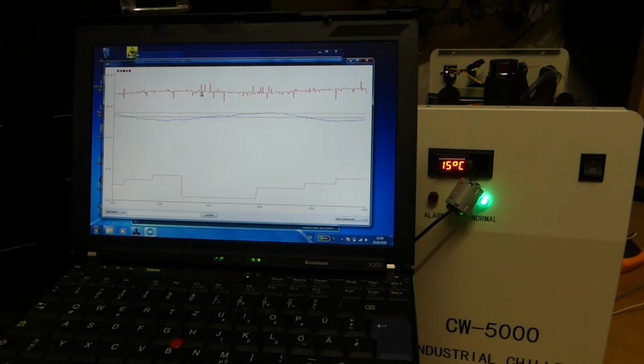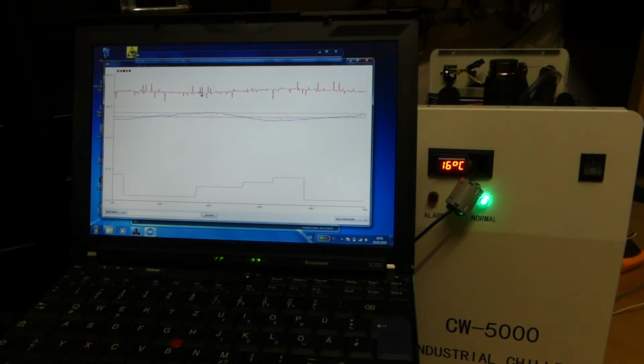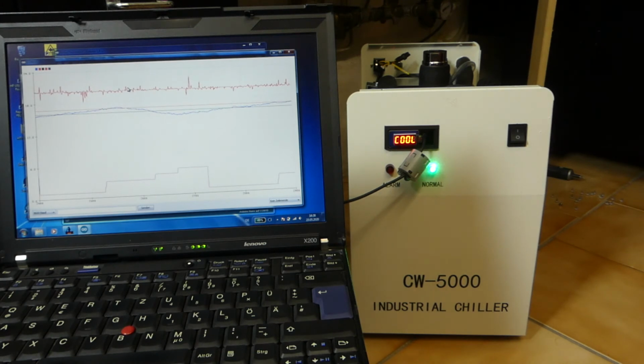Yeah, this is working really nicely. This is just the way I wanted it. The laser's been running for half an hour or so now, and the chiller is working absolutely perfect. The temperature curve that I'm getting on the output is within about 0.8 degrees Celsius, and I have a hysteresis of 0.8 to the positive and to the negative, and it's holding that absolutely perfect.